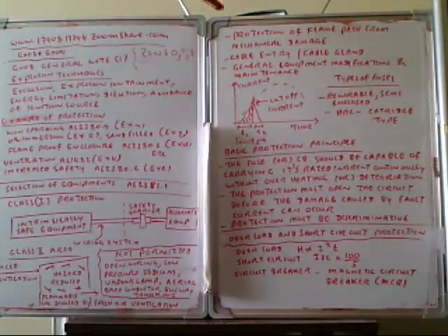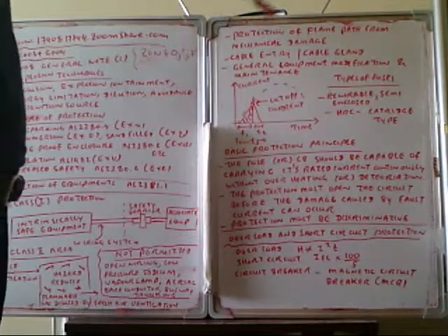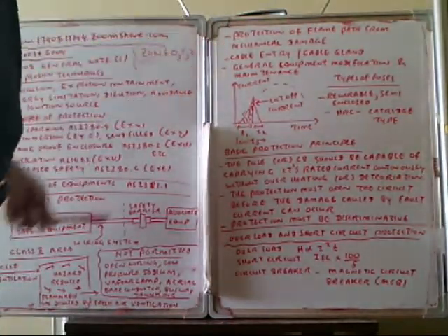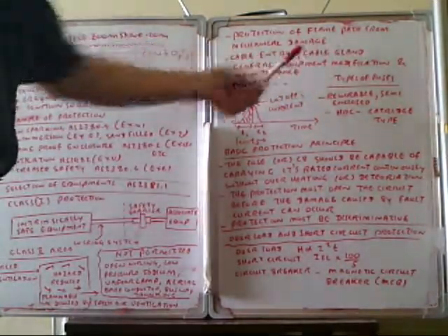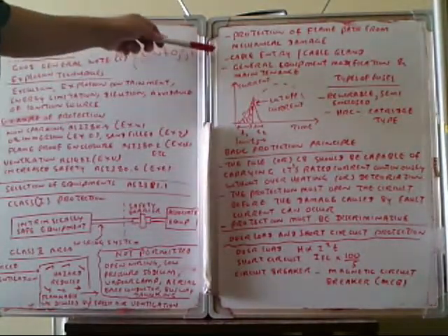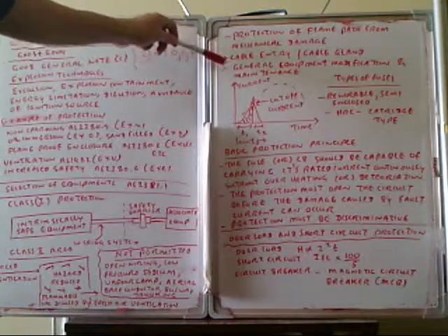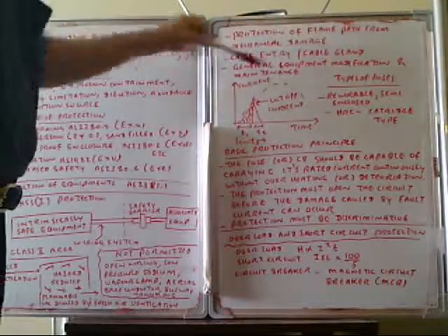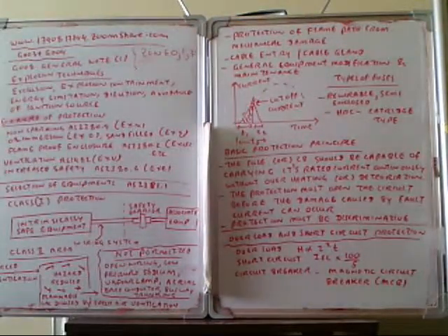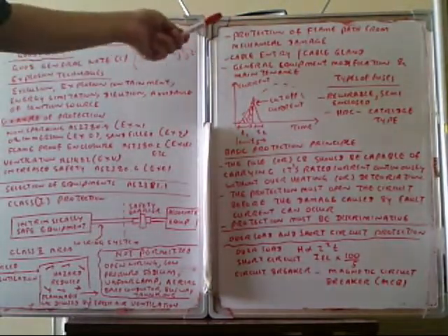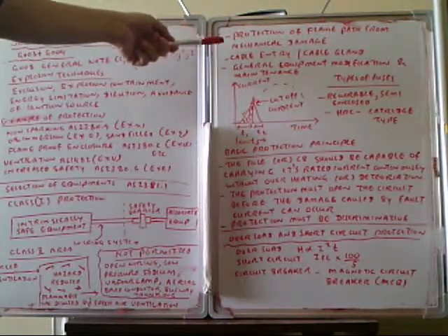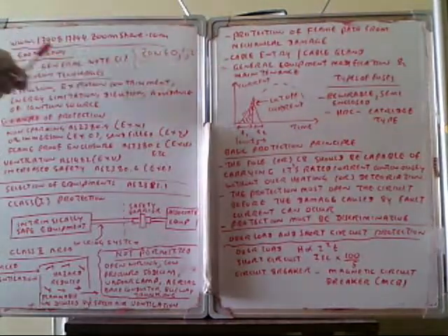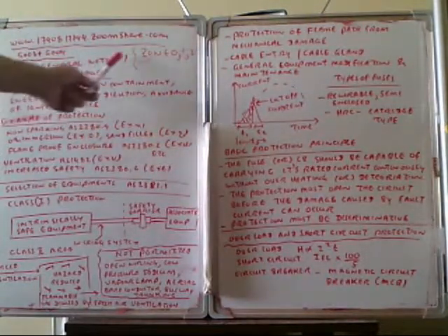We also have to provide protection of the flameproof path from mechanical damage, so the cable entry and the cable clamp need to be properly installed. And we must follow the specific general equipment, modification and maintenance procedures. Those are the detailed procedures for explosion protection. For more details, such as cable clamp connection, cable clamp construction, and general equipment modification procedure, you can read under the G08 general notes 1.